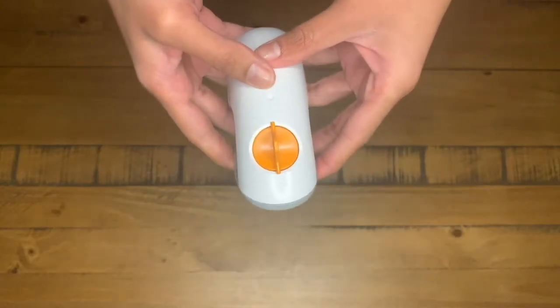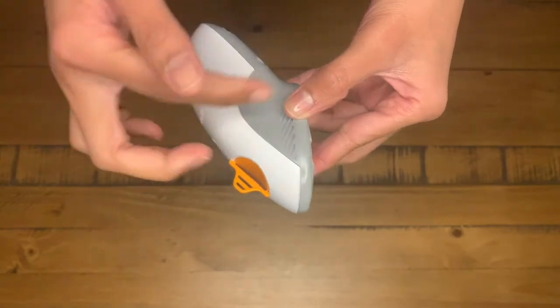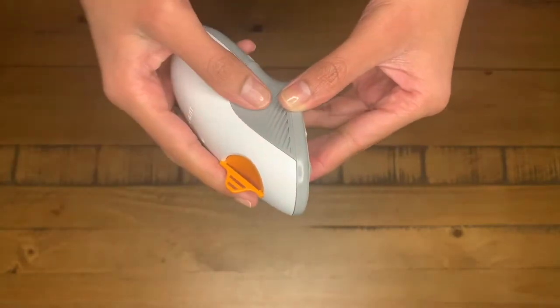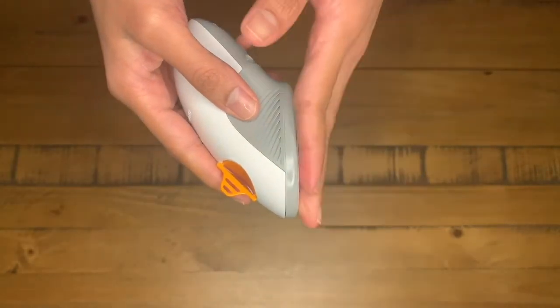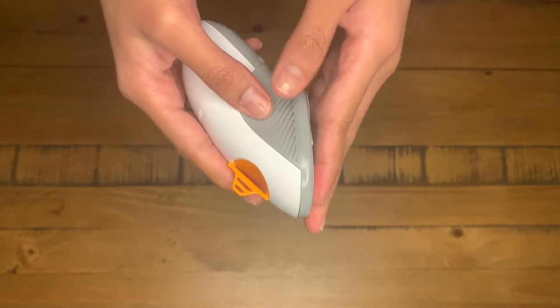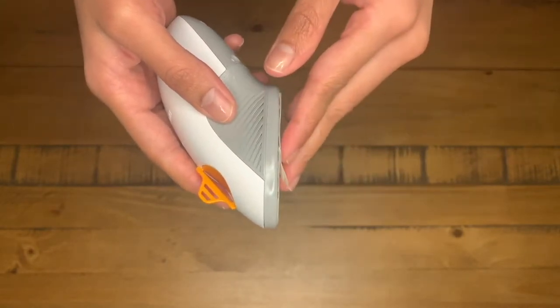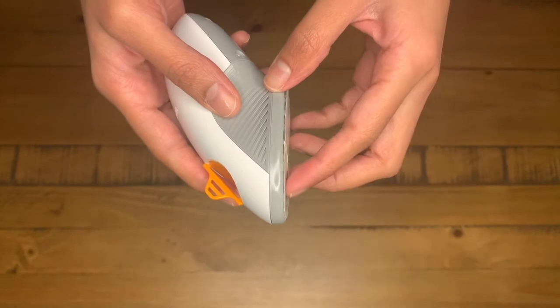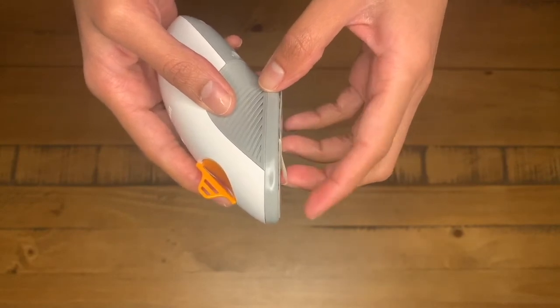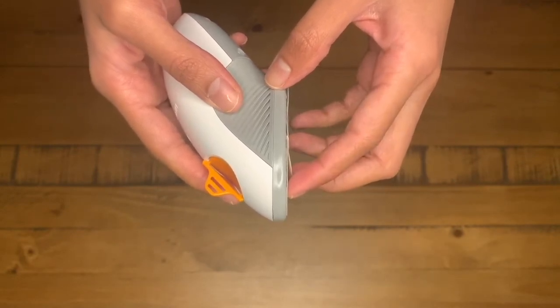Now on to the sensor. The sensor seems really large, however the bulk of this is the disposable applicator. The actual sensor is built into the bottom and is fairly small. This flat part has the adhesive, and it also has a unique ID number similar to the transmitter, so be sure to keep the adhesive cover or keep your boxes, as the needed ID numbers are on the packaging.